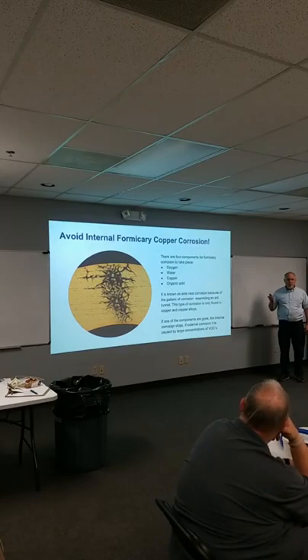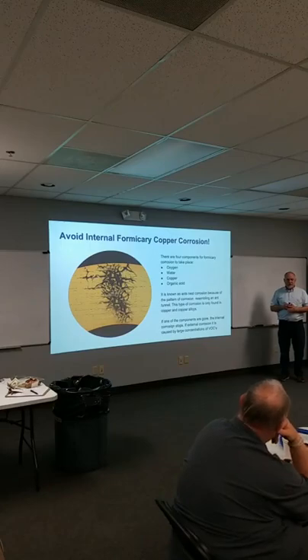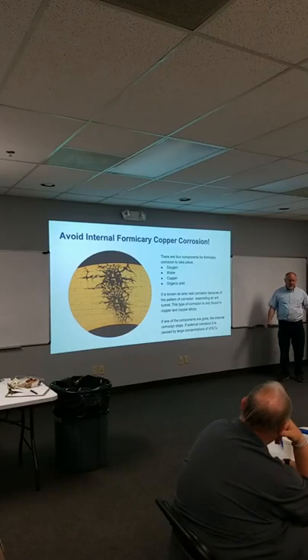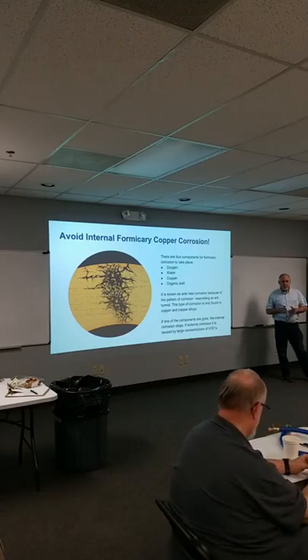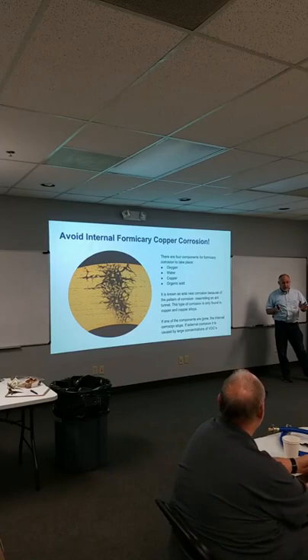You guys remember Copeland having the compressor additives and all the TXVs going bad, right? Copeland had a compressor additive. There was a rash, about, I don't know, maybe 5 or 6 years ago, of TXVs just failing everywhere. Thousands of them. Residential systems, thousands of TXVs failing. Copeland put a rust inhibitor inside their compressor oil, right? They're like, this will be good, I have this rust inhibitor, this is awesome. They tested it for 2 years, no problems. Roll it out in the field, and it's like the shit hit the fan.